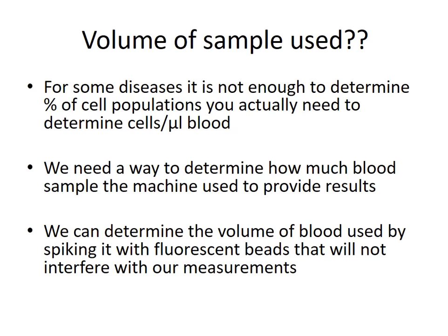put a blood sample onto a flow cytometer, you don't actually know how much volume of blood is being used. And this is a difficult scenario because diagnosis of certain diseases will be that a certain number of cells per cubic millimeter of blood will indicate disease. So the challenge we have is in order to get this information, we need to know exactly how many cells were detected per cubic millimeter of blood. And in the standard flow cytometer, there's no actual way to measure the volume used.